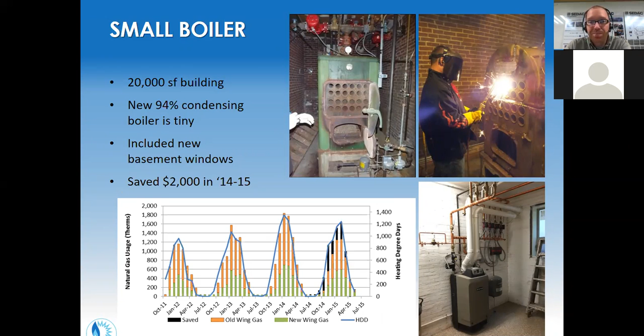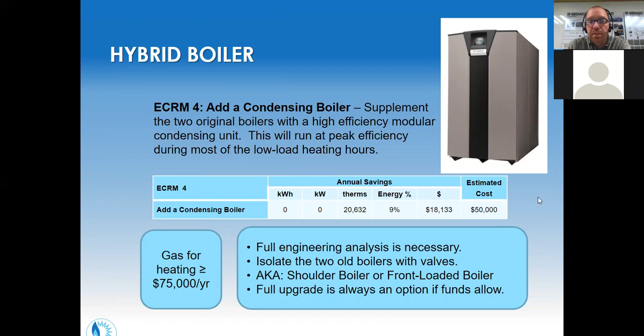Hybrid boilers add a bit more detail - putting in condensing boilers in addition to standard efficiency boilers that might already be there, especially if those are newer. You can run the two together, and these high efficiency boilers can take the bulk of the load hours for the year, resulting in some pretty significant savings.